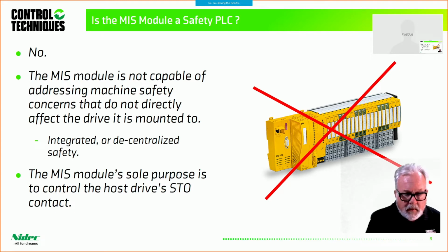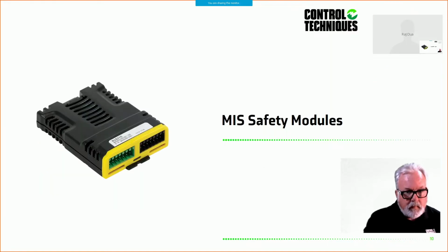And in fact, its only purpose in life is to control the host drive's, either a Unidrive M700 or a Digitax HD's, safe torque off contact. That's what it can do. So not to be confused, can you replace this safety PLC with an MiS 250? In most cases, no. It is specifically designed for the drive it's mounted to.